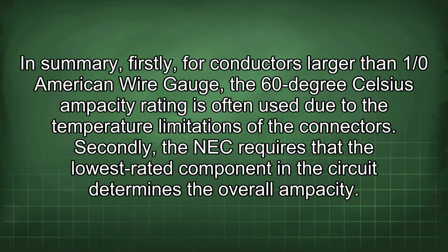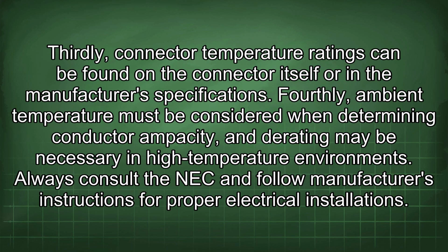In summary, firstly, for conductors larger than 1/0 American wire gauge, the 60°C ampacity rating is often used due to the temperature limitations of the connectors. Secondly, the NEC requires that the lowest rated component in the circuit determines the overall ampacity. Thirdly, connector temperature ratings can be found on the connector itself or in the manufacturer's specifications. Fourthly, ambient temperature must be considered when determining conductor ampacity, and derating may be necessary in high temperature environments. Always consult the NEC and follow manufacturer's instructions for proper electrical installations.